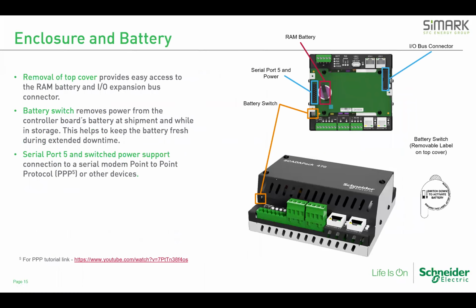New to the 470 and 474 is the inclusion of a battery switch. The controllers have an onboard battery to maintain program and configuration, capable of doing so for about 2 years continuously if power is removed. Previously, this battery was installed from the factory and could degrade if warehoused for a while. The new units include a battery switch and a sticker on the cover reminding you to flip the switch when you receive the unit, connecting the battery to the circuit board to protect your program and application memory in the event of a power loss.